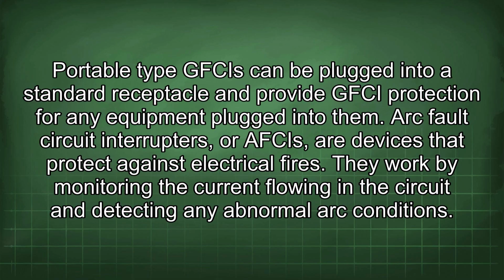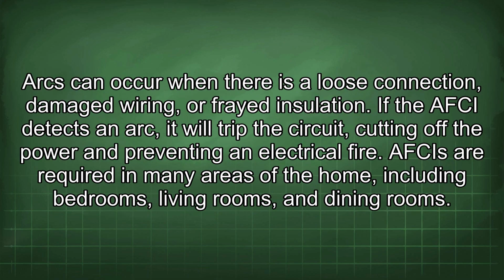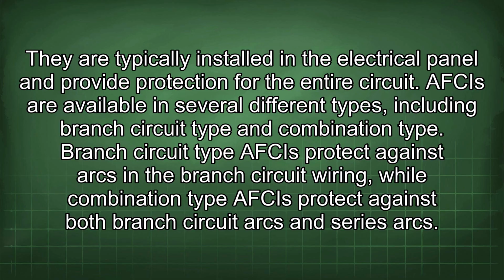They work by monitoring the current flowing in the circuit and detecting any abnormal arc conditions. Arcs can occur when there is a loose connection, damaged wiring, or frayed insulation. If the AFCI detects an arc, it will trip the circuit, cutting off the power and preventing an electrical fire. AFCIs are required in many areas of the home, including bedrooms, living rooms, and dining rooms. They are typically installed in the electrical panel and provide protection for the entire circuit.